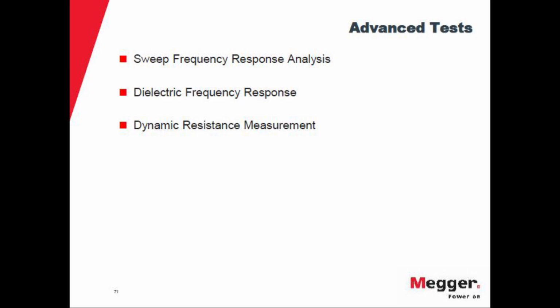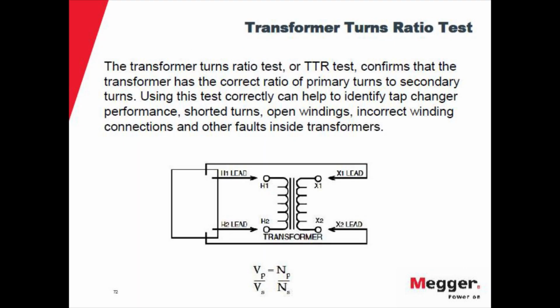And you have additional testing that is more like advanced tests. So you can have a sweep frequency response analysis, dielectric frequency response. This is for the insulation quality, to see if the insulation is in good shape. The sweep frequency response is to determine if there's any mechanical change inside the transformer. And dynamic resistance measurement is to determine the condition of the tap changer if you have an on-load tap changer.